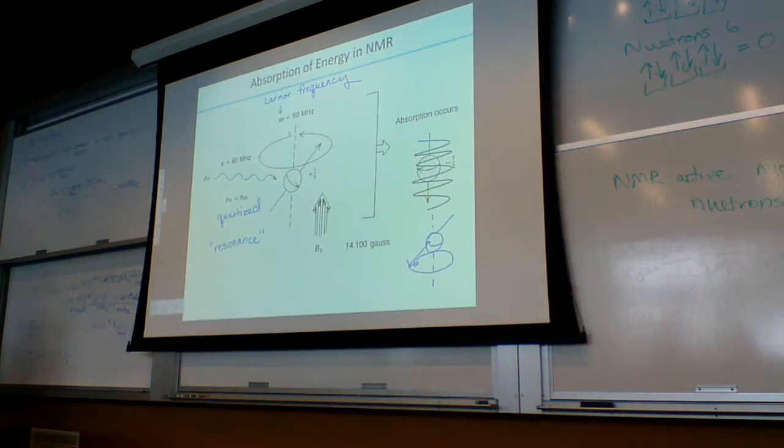Essentially, what I was trying to do was get it to be the right frequency for the magnetic field. The magnetic field can drift a little bit, and so every once in a while we have to adjust our frequency to be on that signal that it was looking at. So I was actually looking at the deuterium in the sample, and I was getting it to match that, and then that makes it match all along.